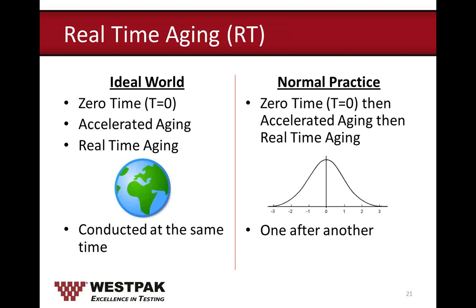It's already difficult for a customer to generate enough samples for zero-time testing, let alone provide additional samples for accelerated aging and real-time aging. Once they pass zero-time testing, they start accelerated aging but hold off on real-time aging until the first aging study is completed and passed. A handful of times, customers who passed zero-time testing have failed accelerated aging due to aggressive temperatures or temperatures not appropriate for their materials.